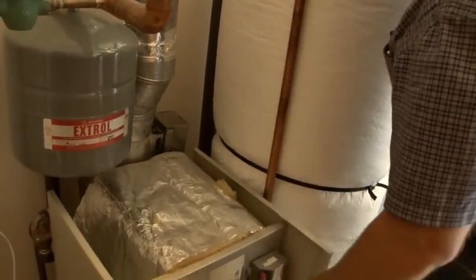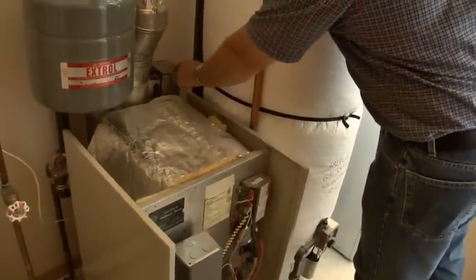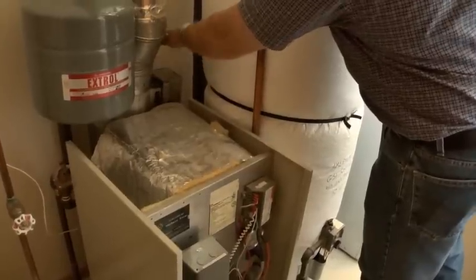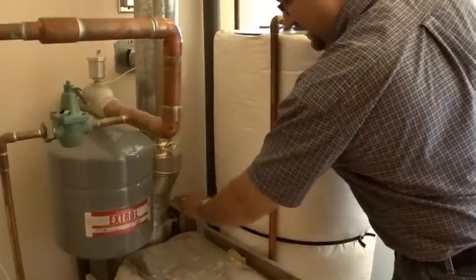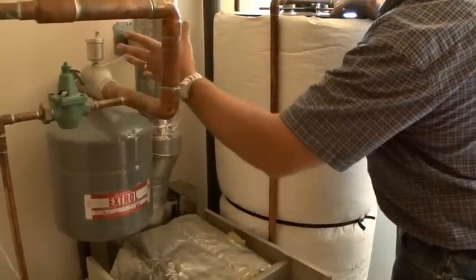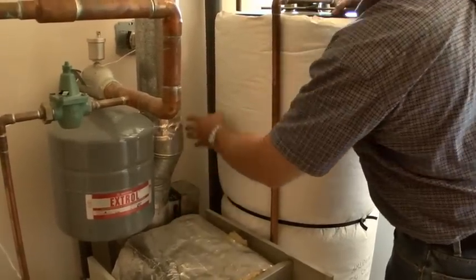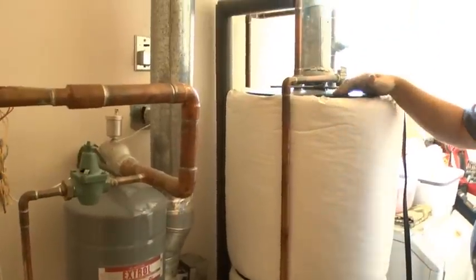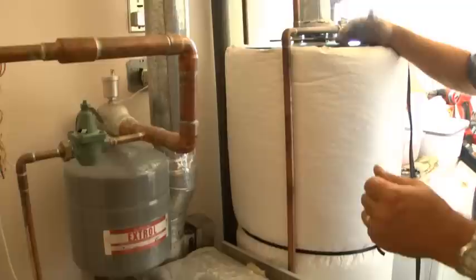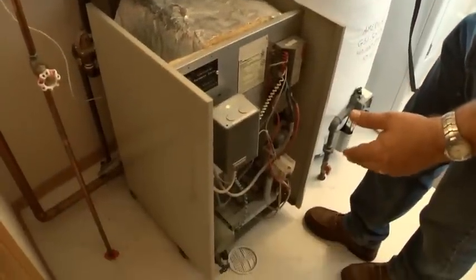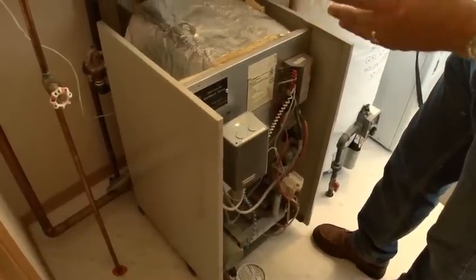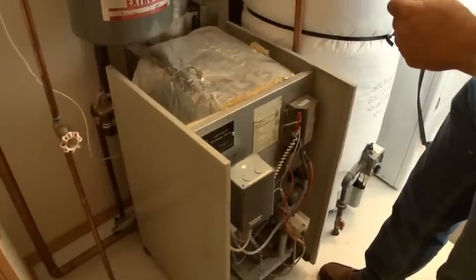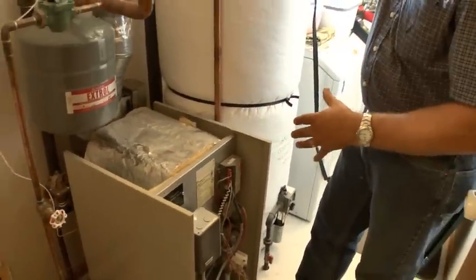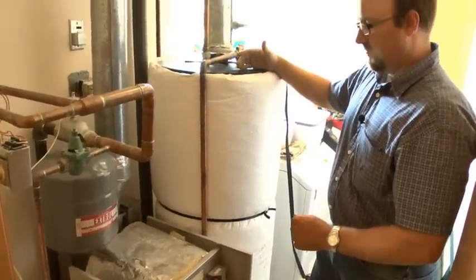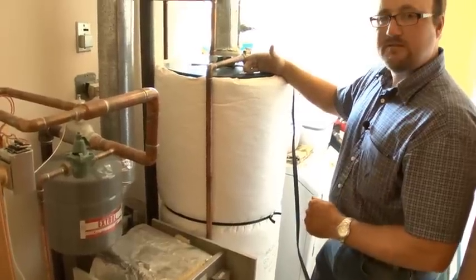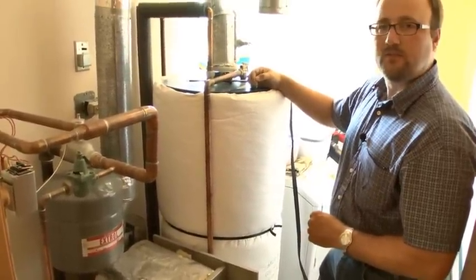Well, during those periods when that flame's off and we still have a call for heat, this shuts off the flow of any heat from rising up through here. So this would shut off. It keeps that heat inside the boiler so that it can be delivered to the house. With this locked open all the time, that heat rises up through here. So on this heating system, we can gain some efficiency. We can solve some safety issues, but overall, this is a pretty good running system. We don't have a carbon monoxide issue. The amount of gas and air mixture when the doors are all open are just fine. So those are the things that need to occur on this heating system to get it into a little better shape than what it is.